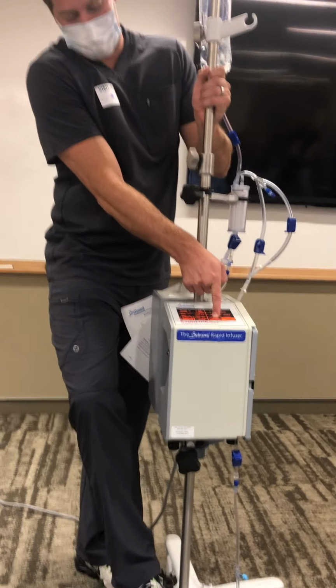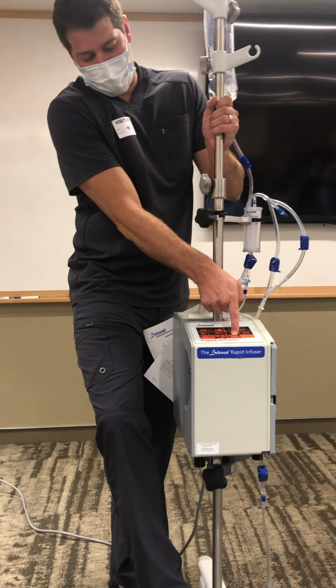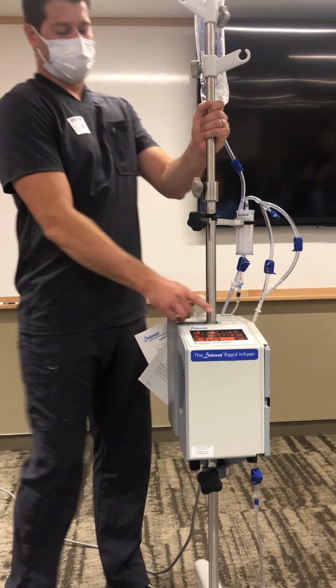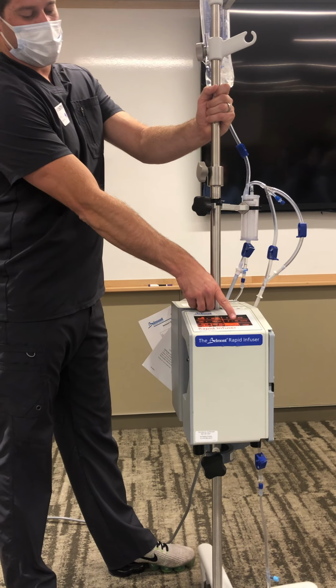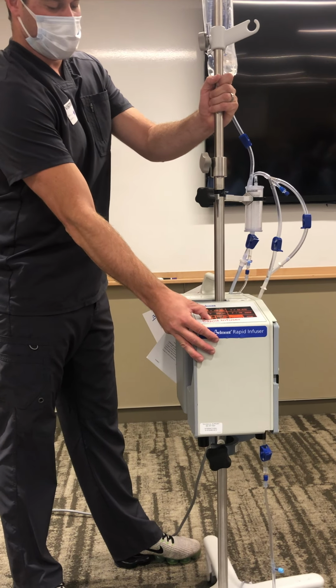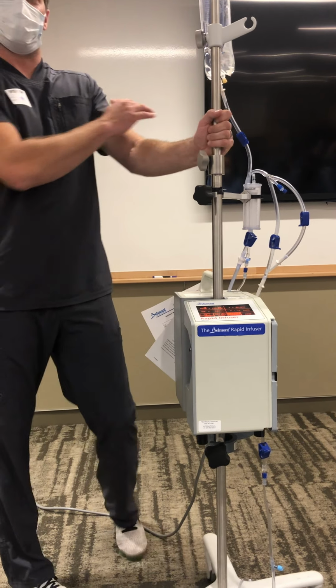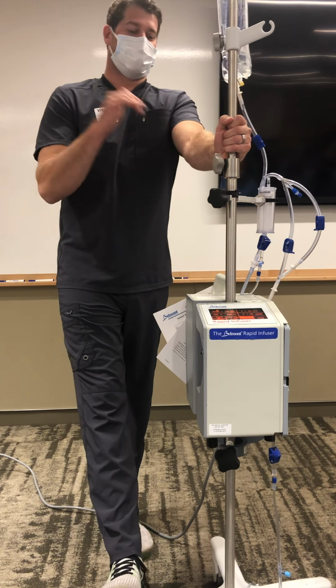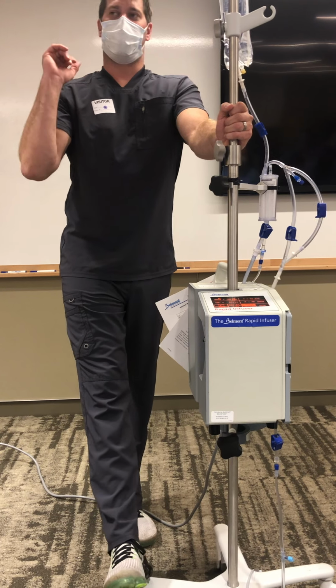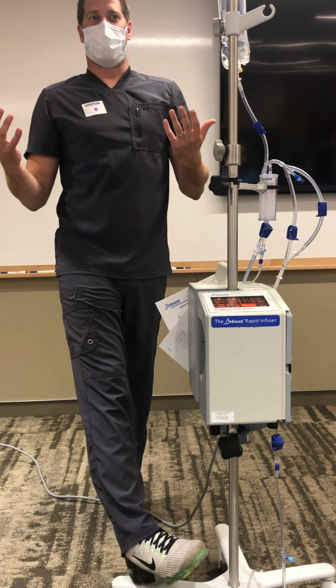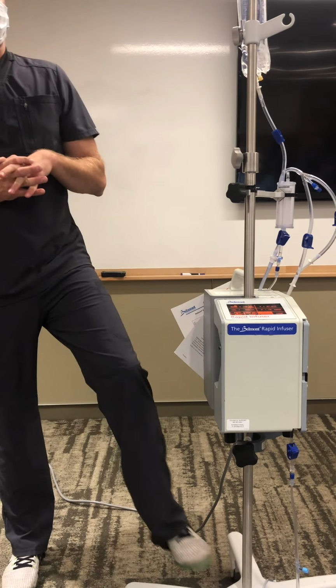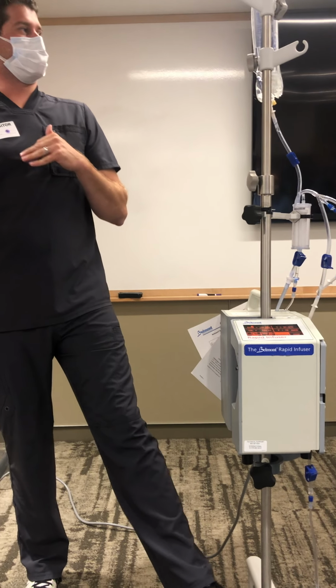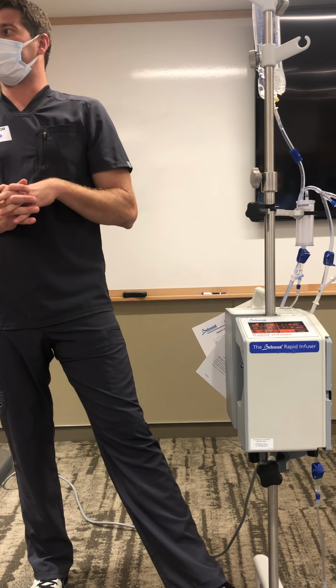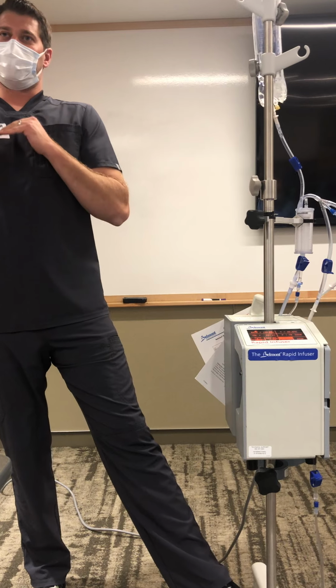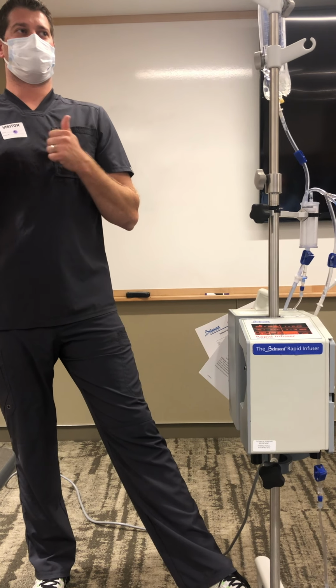These options will come up, so say I wanted 200 and missed it—it'll come right back around to me. 200 is my target, and that's how far into the target I am. I still have control over how fast or slow I want to deliver that 200. But the takeaway is once we hit our target, in this case 200, it'll beep, stop, and go into standby mode, not doing anything else until you tell it what to do next—another bolus, regular infusion, or nothing at all. That's your choice, but again, it's for delivering specific amounts of fluid.